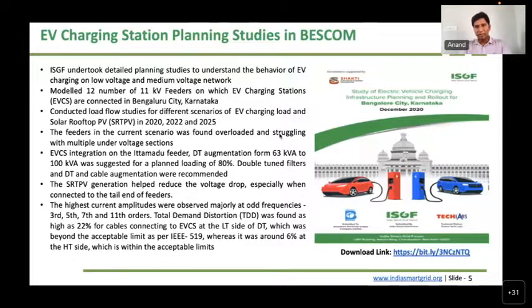We did not consider EV before, and under current conditions they were facing issues. For EVCS integration, there's one important feeder from the study's perspective where we found that we need to augment the existing DT from 63 kVA to 100 kVA, along with several other recommendations. We assumed the load is at 80%, and there were recommendations on how to arrest the harmonics generated on the feeder due to the EV charging station, along with mitigation of several other issues we are facing.